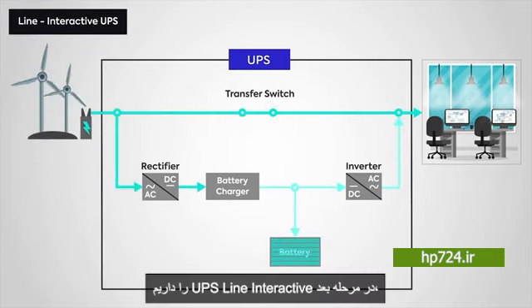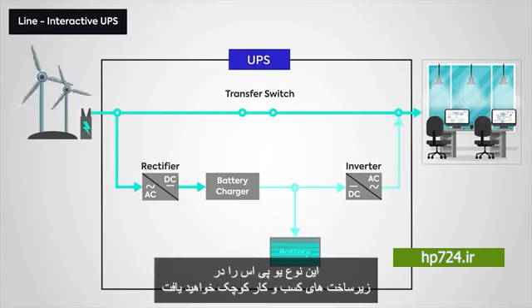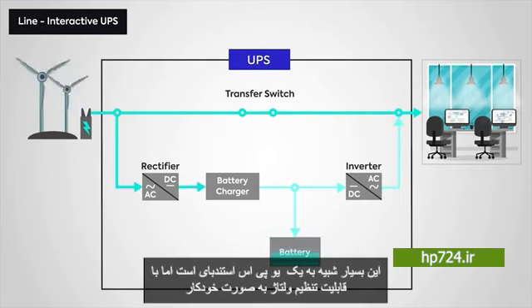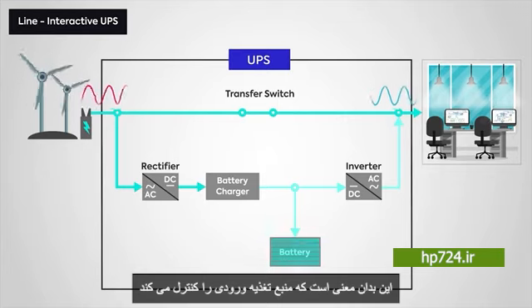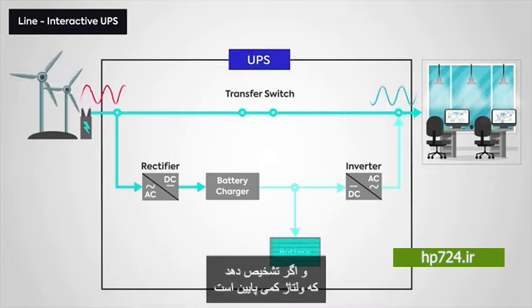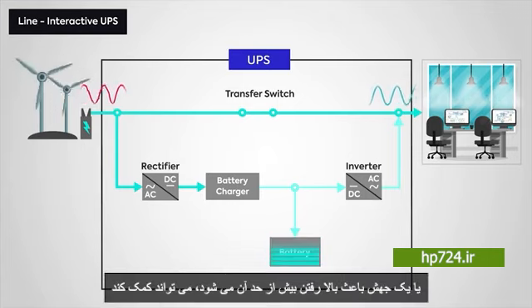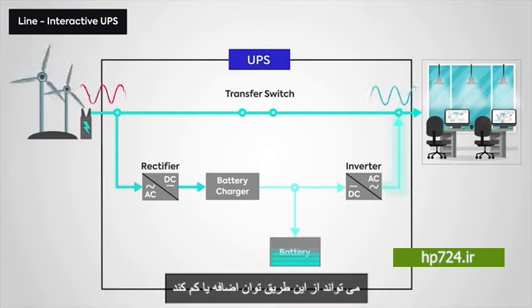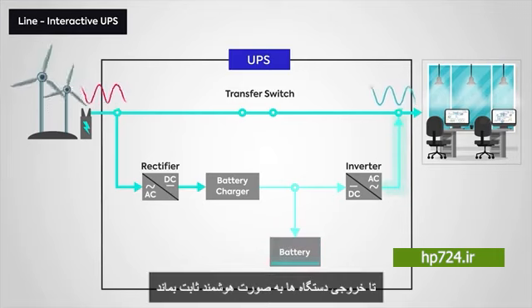Next up, we have the line interactive UPS. You'll find this type of UPS in small business infrastructure. It is very similar to a standby UPS, but with the added ability to regulate voltage automatically. This means that it monitors the incoming supply and can help out if it detects that the voltage is a bit low, or a spike is causing it to go too high. It can add or subtract power in this way to make the output to our devices constant.